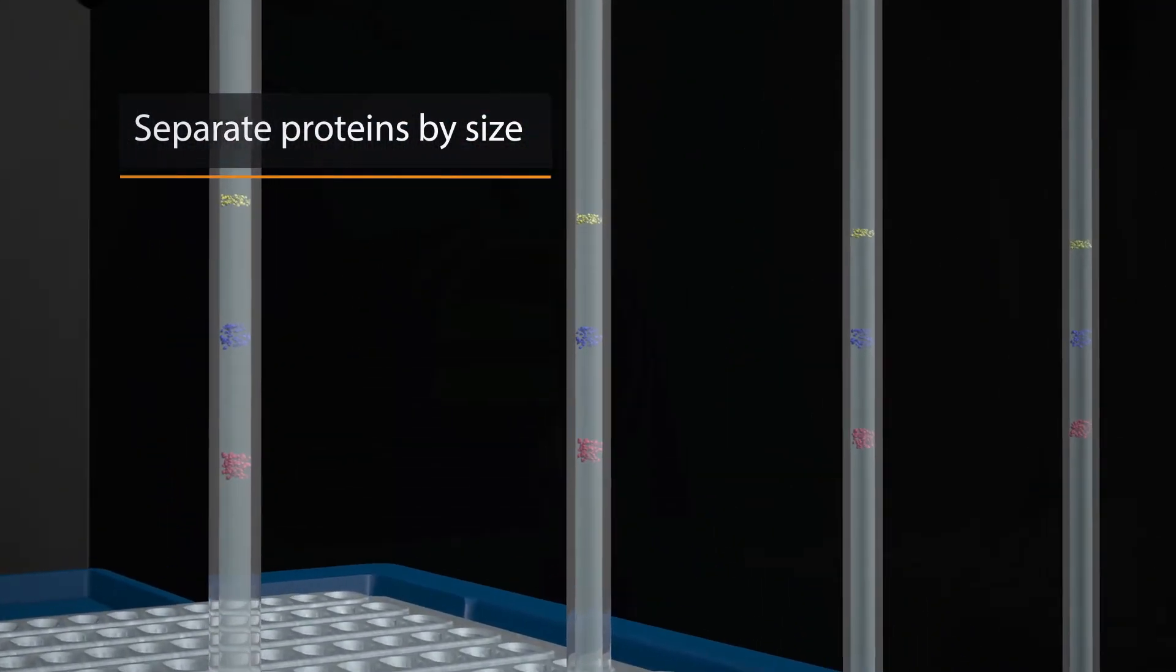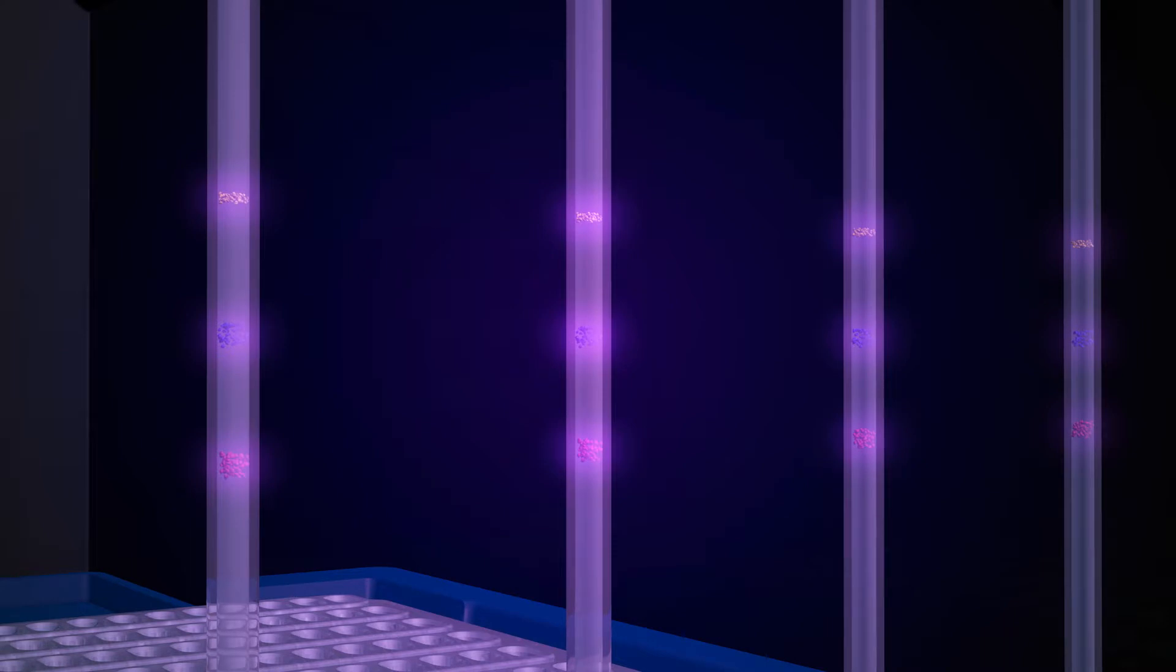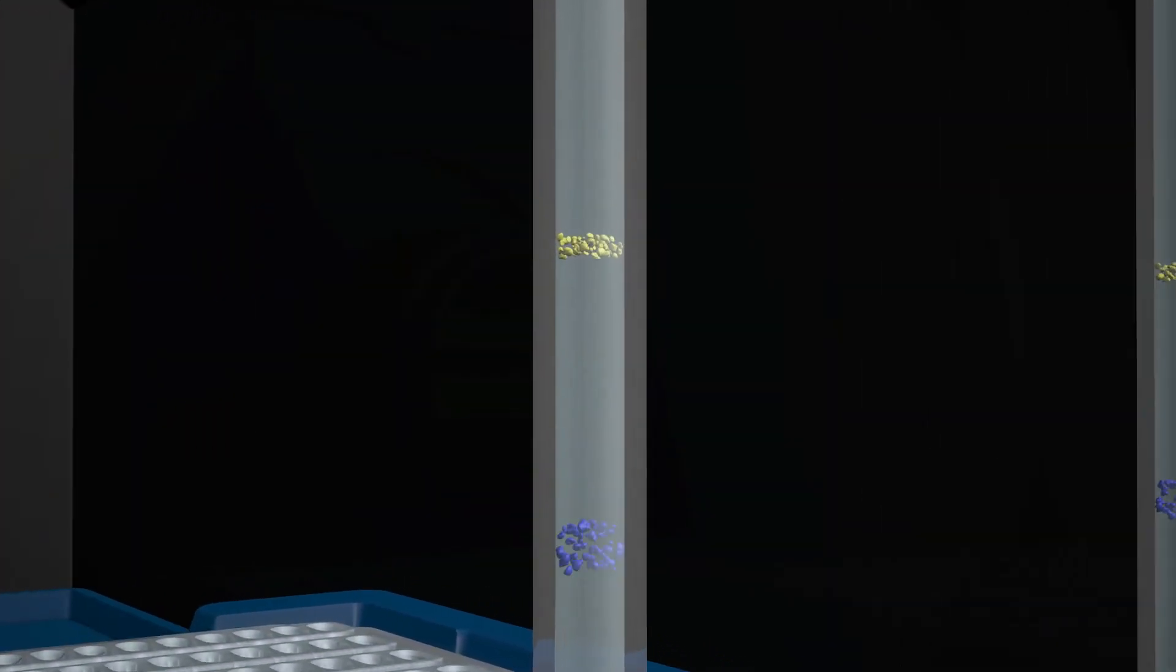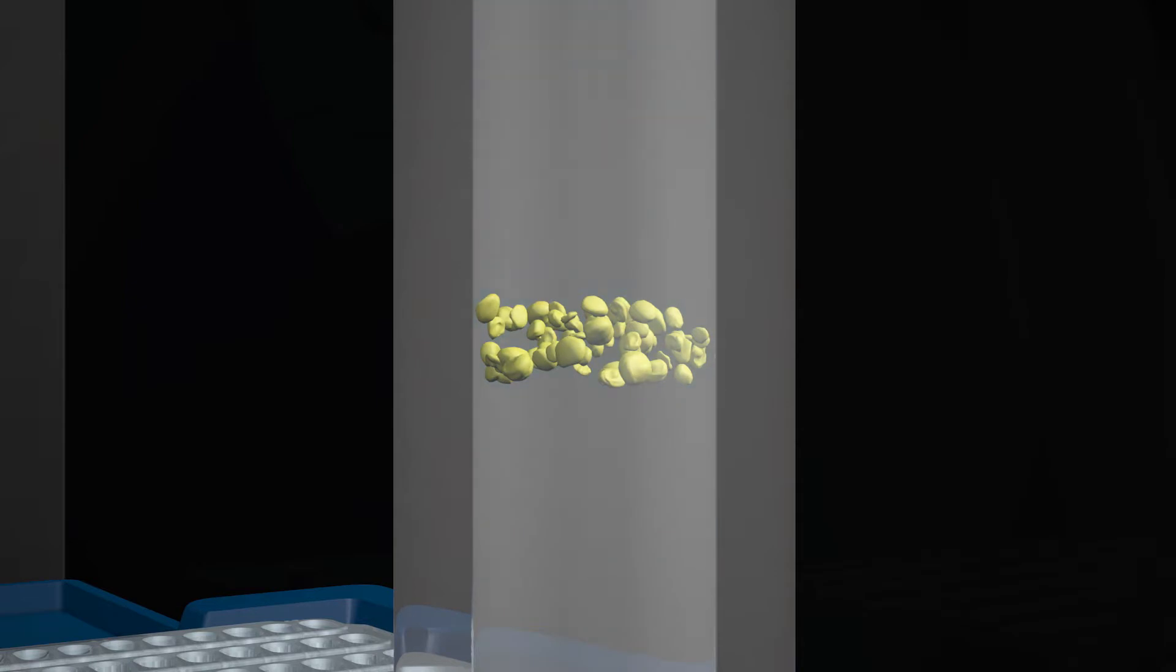Once the separation is complete, UV light immobilizes the proteins to the capillary wall. With proteins now immobilized and the matrices cleared of the capillary, Wes starts the immunoprobing.